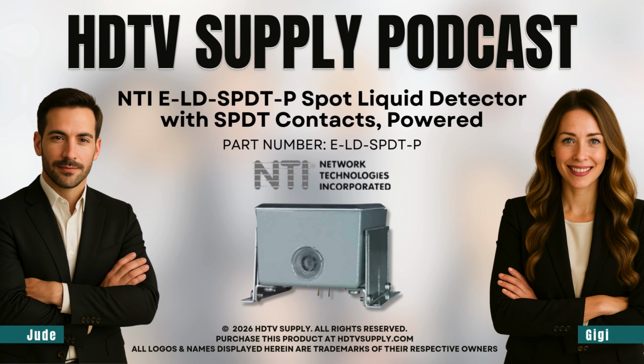So the device is tough and precise, but how does this little sentinel actually report back, especially in a huge facility? That's the integration piece, and it's really clever. It provides what are called SPDT alarm contacts, single pole double throw. What it means is the detector can do two things at once: send one signal to the main control room's monitoring system for logging and automated alerts, and at the same time trigger something locally, a siren, a flashing light, maybe even shut down a specific pump. You get an immediate local response and the central alert, which is key for cutting down response time.